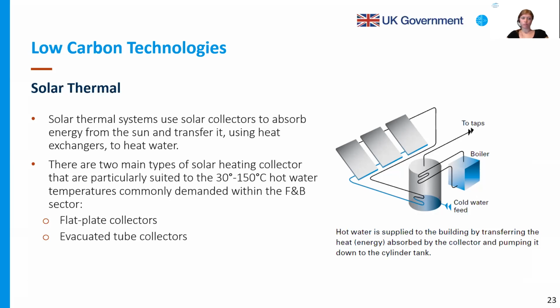Evacuated tube collectors. So these are slightly more complex equipment in terms of, these tubes need to be evacuated and backfilled with working fluid, same as the heat pipes that we saw earlier, right? Although they are slightly more cost intensive, they offer the advantage of being used for a wider range of temperature operations, from 50 all the way to 150 degrees Celsius. And their thermal efficiency is around 80% effectiveness. Yeah. So we move on to the next slide.